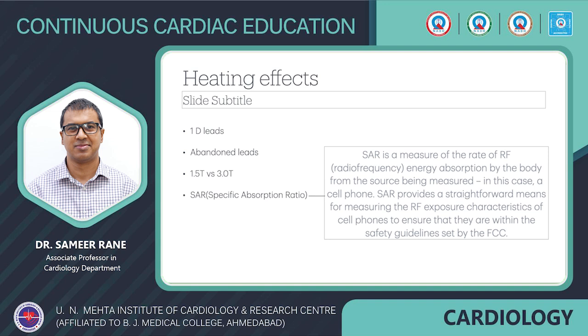An increased specific absorption rate, which is a unit, is associated with a higher risk of thermal injury. The specific absorption rate increases with the square of the increase in the magnetic field strength, meaning a 3 Tesla field causes a fourfold increase in this unit compared to 1.5 Tesla, provided other parameters are kept equal. By limiting the field strength to 1.5 Tesla, it is ensured that patients with CIEDs experience a SAR of 2 or less during the scan.